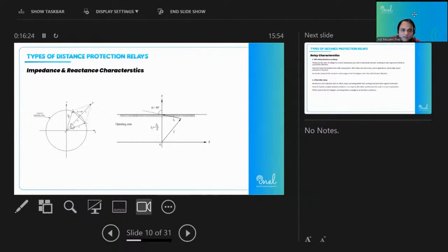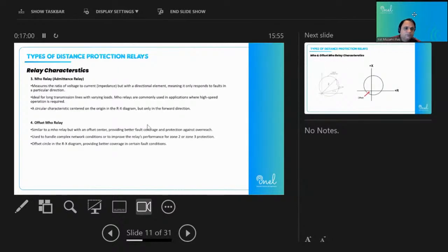So to avoid this resistance issue, this characteristic is used, which is independent of the R values. It only depends upon the X value. We select an X value for that transmission line, whatever it is. If its length is, say, 5 kilometers, then as per 5 kilometers we will set its X value, but it has an infinite resistance value, which will tackle the arc resistance, and also any fault resistance other than the arc.